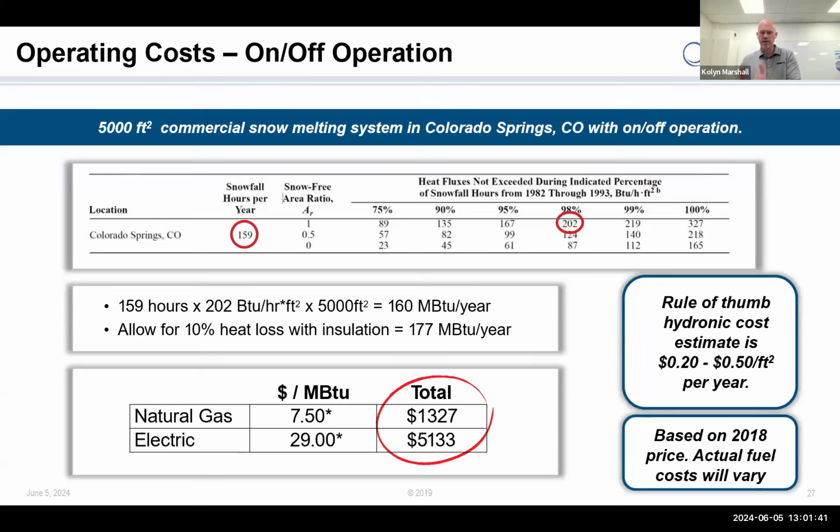Though I have a 140 and a 110 on supply and return, the temperature in between is even all the way along that loop. And you get a much more even melting earlier. They both will melt eventually and clear the space. It just depends upon what your performance factor is from a design standpoint.